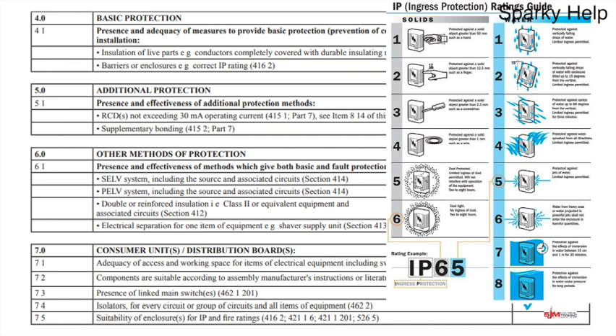So if we take the IP2X we had earlier, why do they say that? Well, they're only interested in the solids, and if you look at 2, it says a finger, which is 12.5mm in diameter, not length, because that would be a fairly stubby little finger, wouldn't it? They put an X in because they're not interested in the water part. Obviously manufacturers, when they test their equipment, will give it both ratings because they don't know where you're going to use it, so they just give it a rating. It allows you to make the decision.